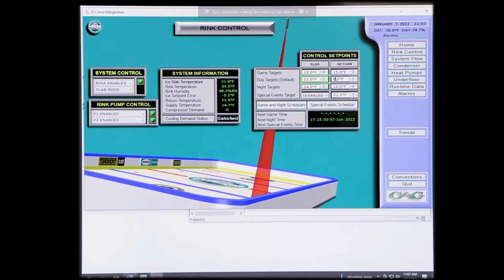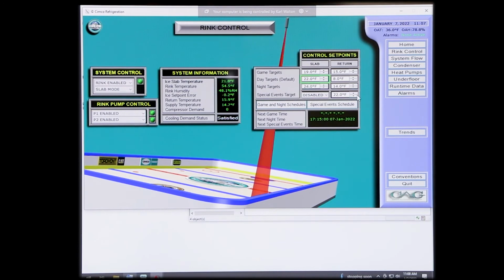Now that is return temperature. So it will literally run the system down to 6 degrees, then shut the compressors off, keeping the pump running in return mode. So if you're having a really, really bad weekend, you've got a ton of stuff going on, it's going crazy, you can always put the system into return mode, simple click, it'll switch to that. That's the coldest that you can possibly run it. As long as you have your compressor demand set for 3, you will bring on all 3 machines, and you will try to maintain that temperature, and it will maintain that temperature.